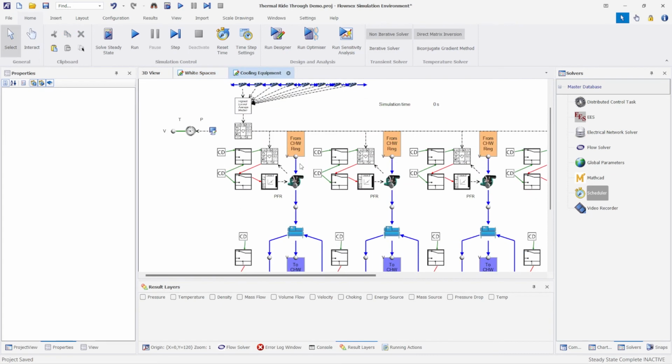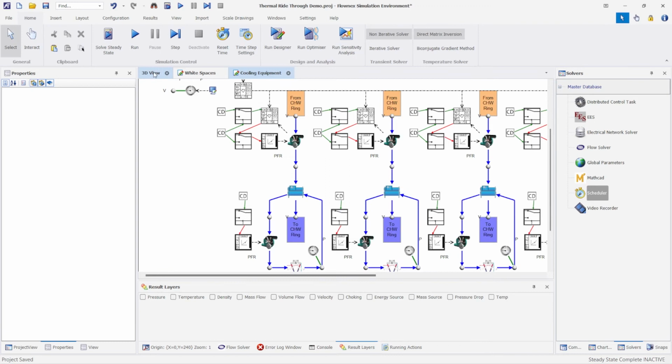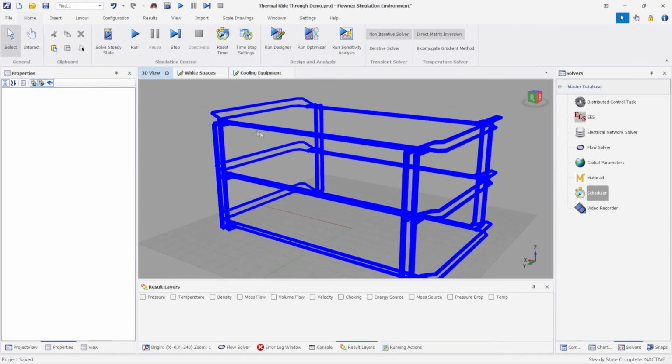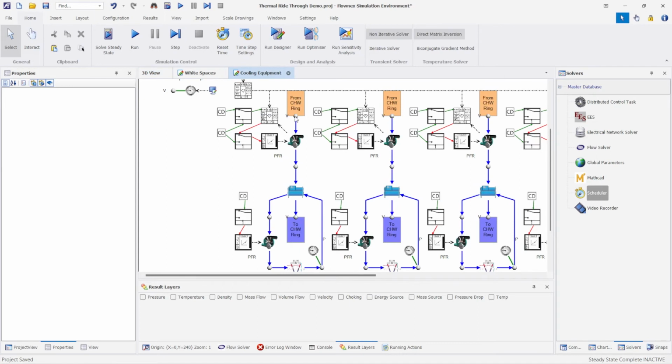So here we're connecting our chillers again to the piping network, but now we're connecting up on the roof of the system. These connections here are again made with these view nodes. We have a chilled water pump that sucks water from the hot ring, passes it through the evaporator of the chiller, and then passes it into the cold ring on the roof.